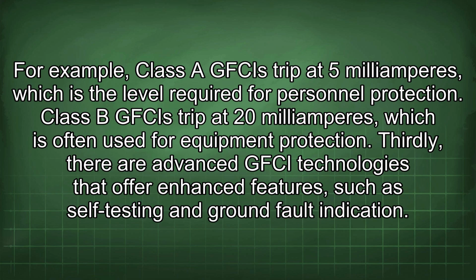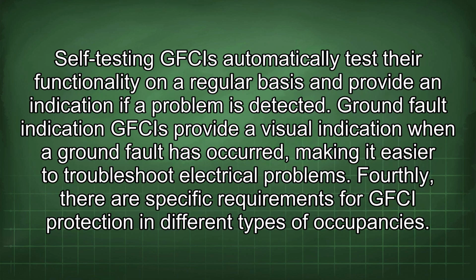Thirdly, there are advanced GFCI technologies that offer enhanced features, such as self-testing and ground fault indication. Self-testing GFCIs automatically test their functionality on a regular basis and provide an indication if a problem is detected. Ground fault indication GFCIs provide a visual indication when a ground fault has occurred, making it easier to troubleshoot electrical problems.